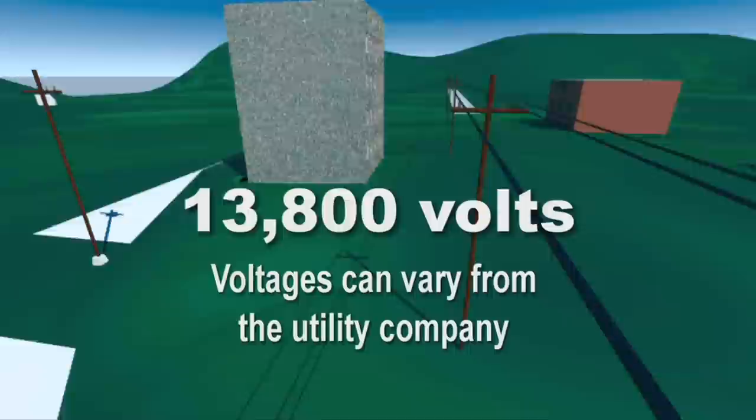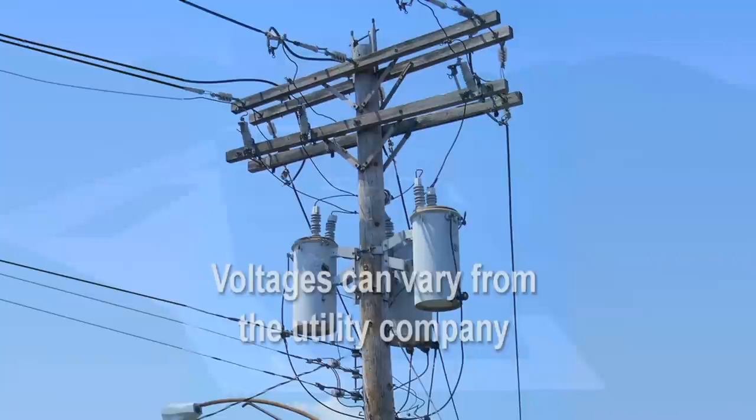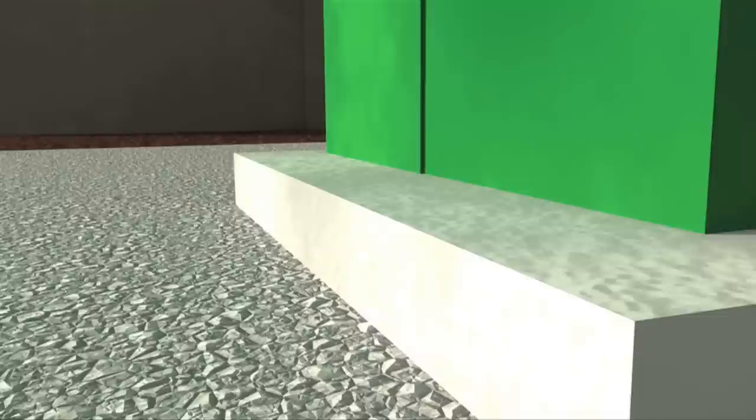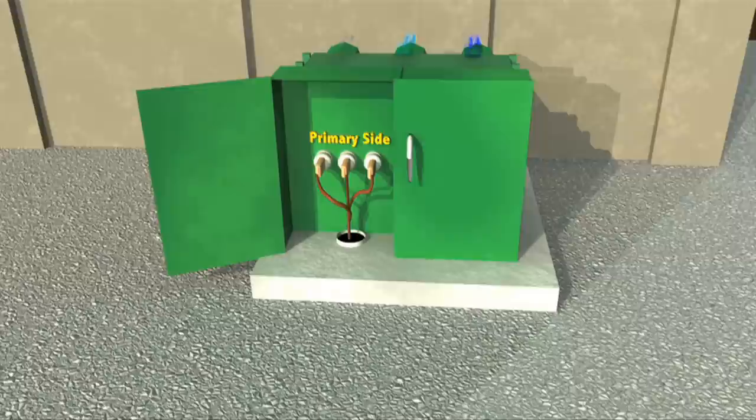In our example, we begin with the utility company supplying 13,800 volts from the road to a utility pole in the parking lot. At the top of this pole, you see three transformers. These transformers will step down the 13,800 volts to 4,160 volts. This voltage is transferred down the pole through copper wires that are encased in conduit. This conduit travels underground and enters the oil transformer on the high or primary side of its junction box.